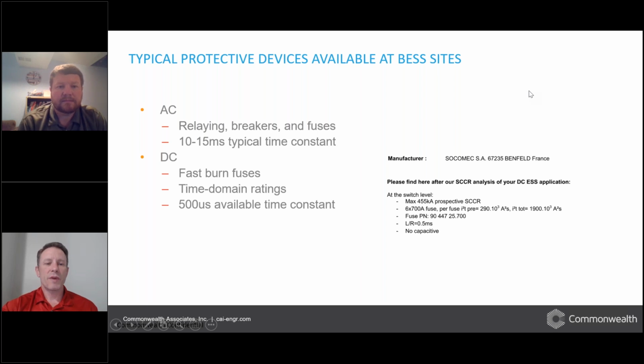So some of the protection we can use on AC, relaying and breakers, there are no relays and breakers that can handle this type of fault current and the speed we need to trip on the DC side. The fast burn fuses are really what we need to use on the DC side, and they are significantly faster than AC fuses ever could hope to be. So our time constant on the AC side is usually in the milliseconds, and DC side it'll be in the microseconds. And on the right, this is the specification of one of the fuses we've used.